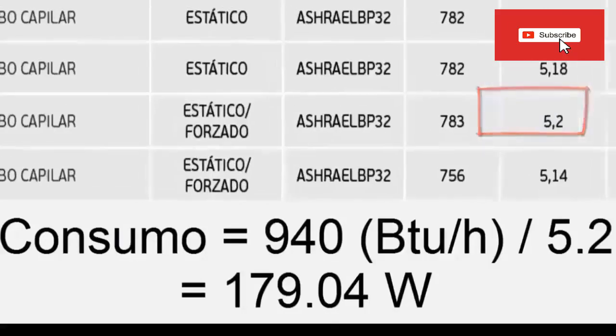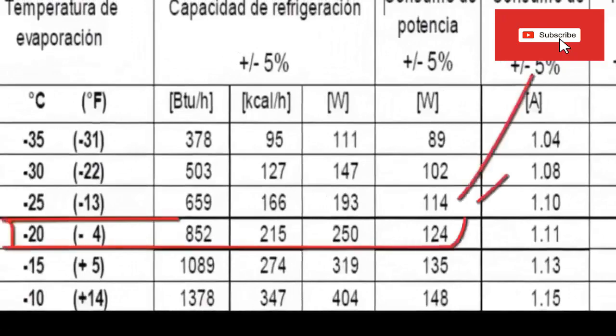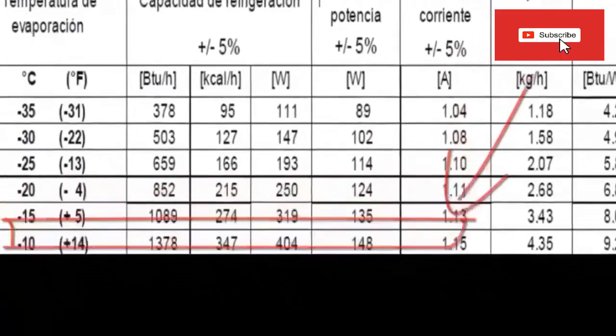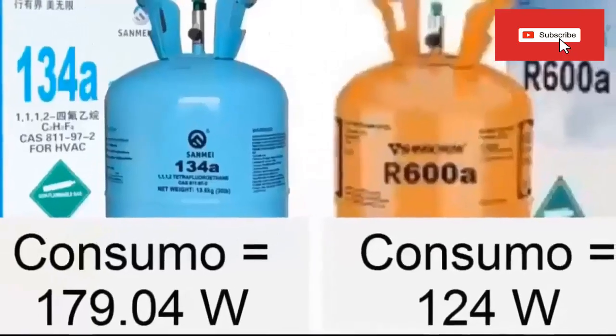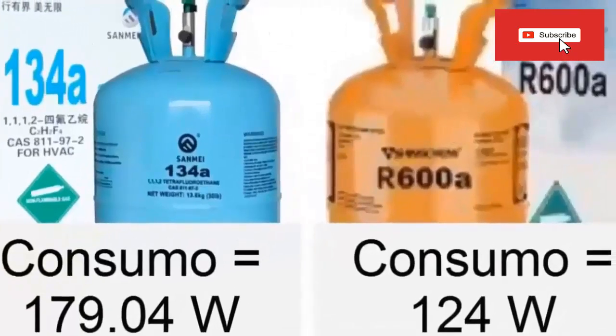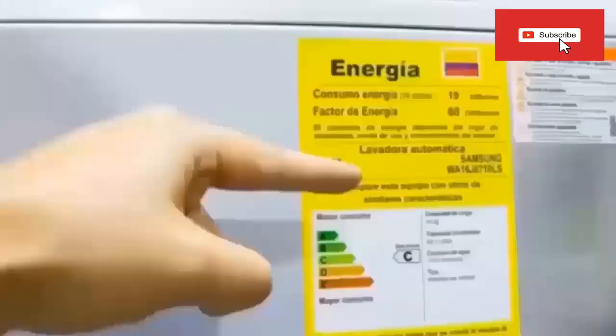For the compressor with R600a, a direct consumption value of 124 W is obtained from the table. As we can see, the energy consumption of the R600a compressor is less than the consumption with the R134A compressor.